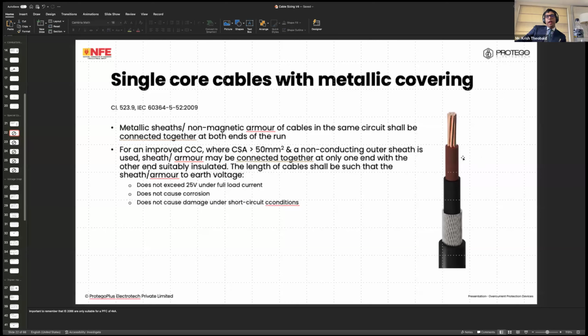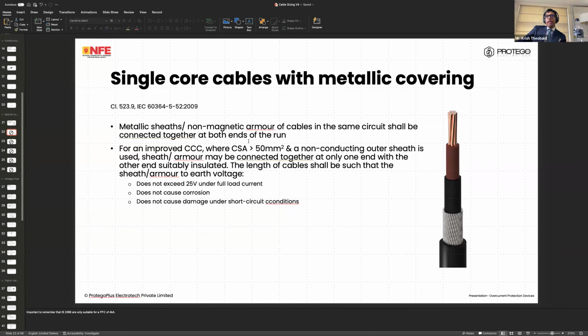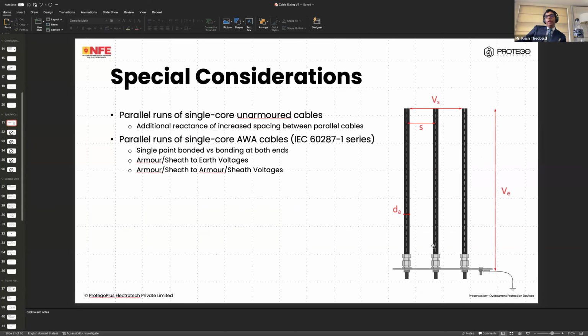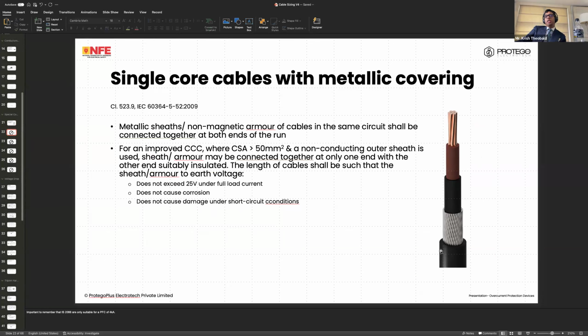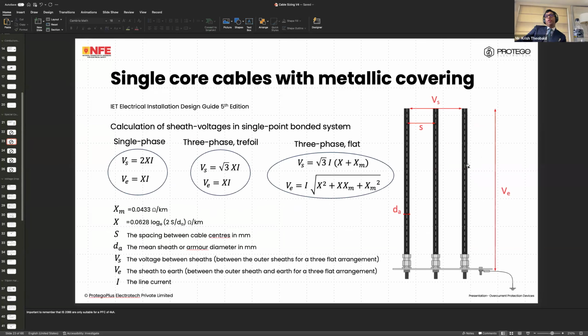See, there are other concerns when cables exceed 50 square mm, and when these cables have metallic sheaths, which are non-magnetic. We need to ensure that the sheath voltage, if they are bonded at a single point, does not exceed 25 volts, and the sheath voltage does not cause corrosion. If you bond on both ends, you are going to have currents flowing within this sheath, which is going to reduce the overall current carrying capacity. So there are calculations given for the sheath voltage. You can find further information in the 60287 part 1-1 and 1-2 on this information.